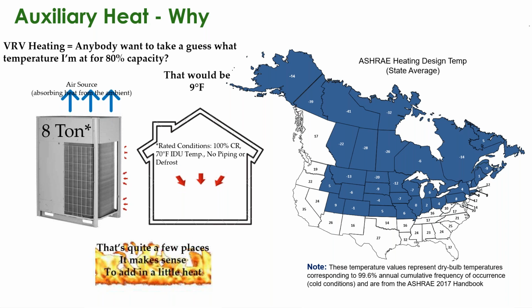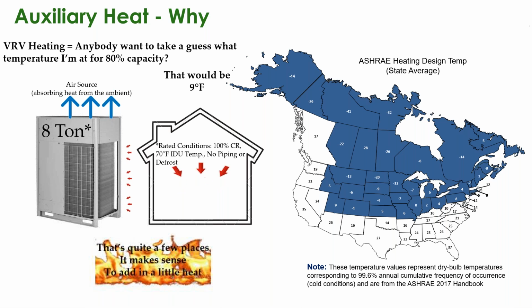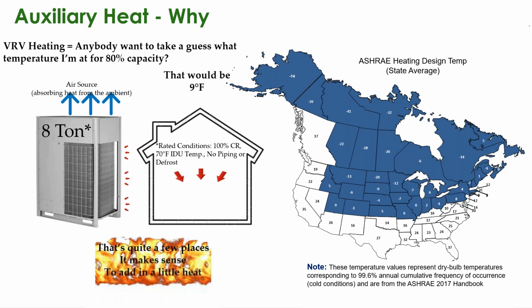So the same kind of rule applies as with every other heat pump system that I've worked with over my years. You want to make sure you're covered on the cooling side and take a look at the cost benefits of how much you can increase the sizing on the heating side. If you go too much to the heat design and size for that, you're adding cost to the job and potentially harming the equipment in the long term.